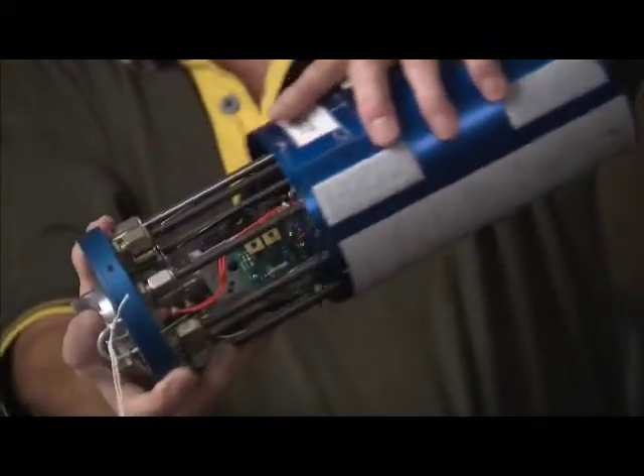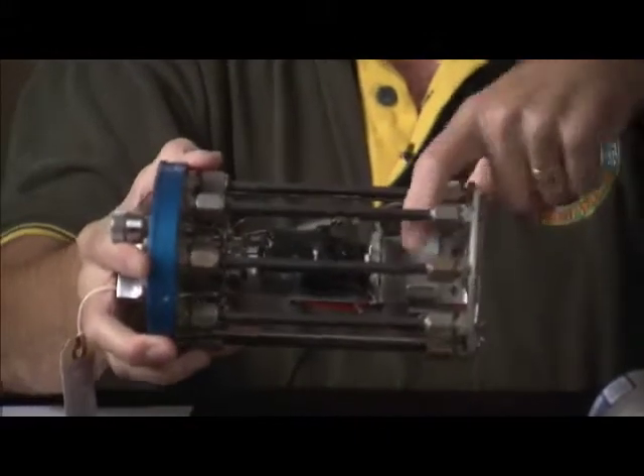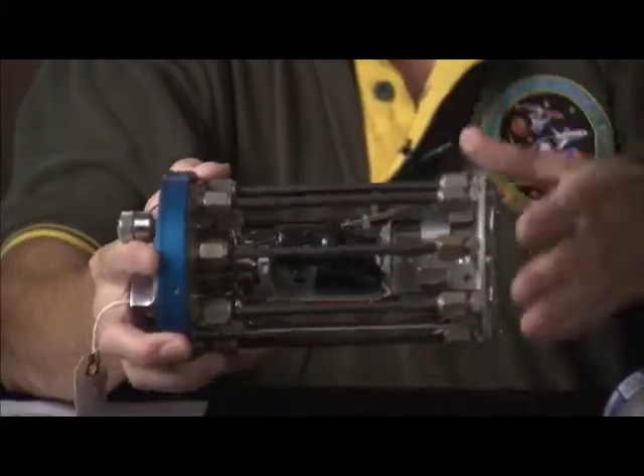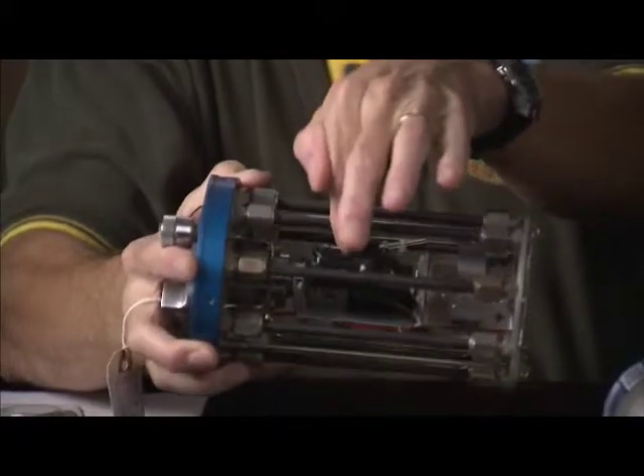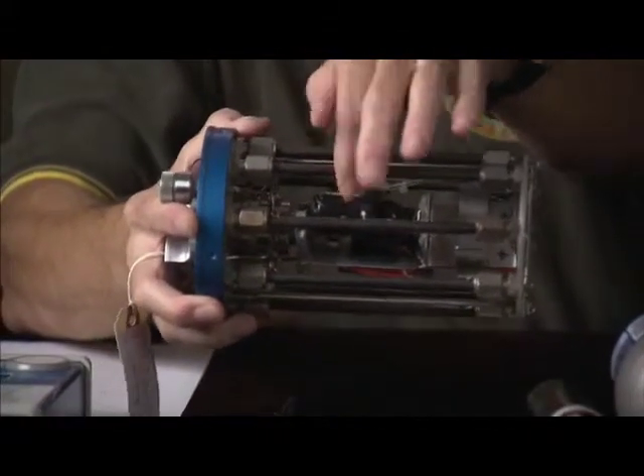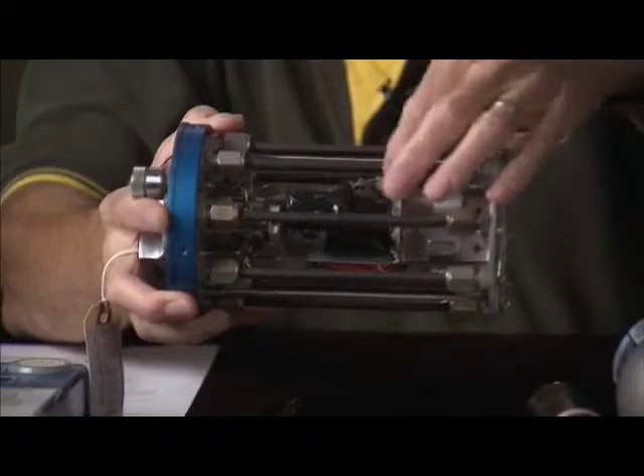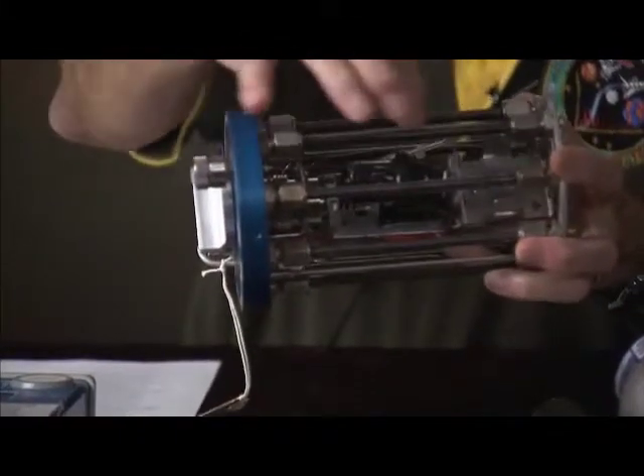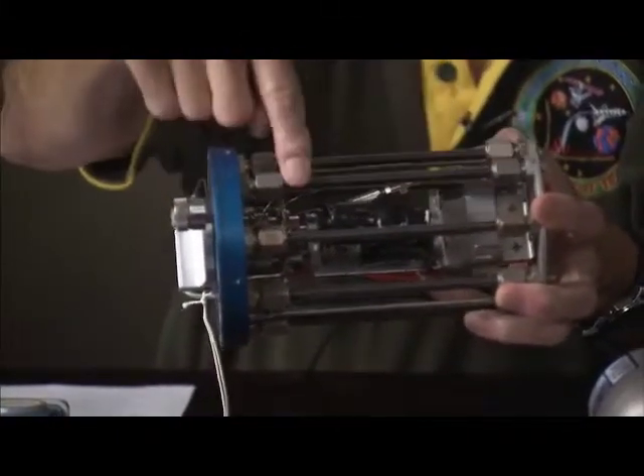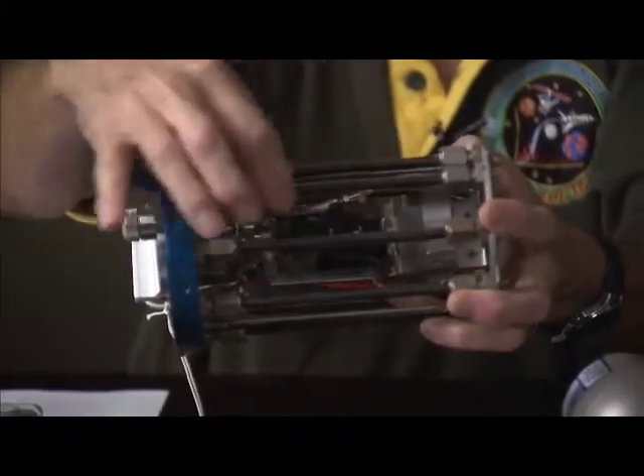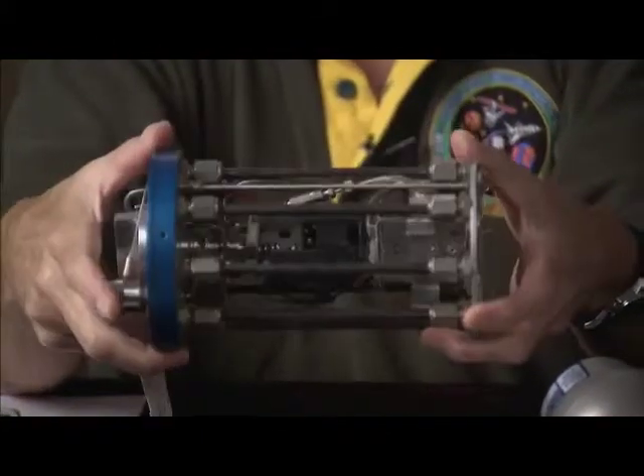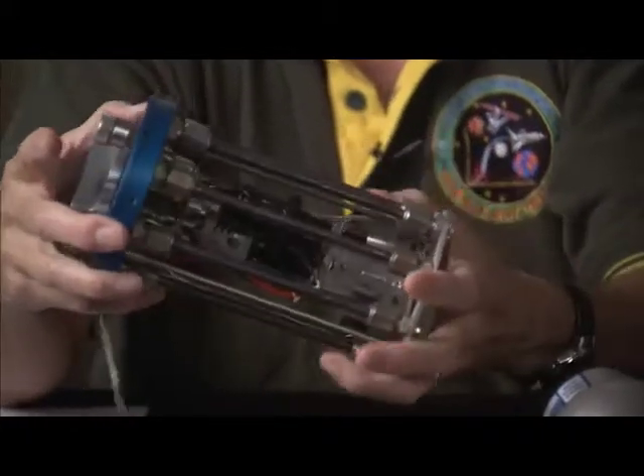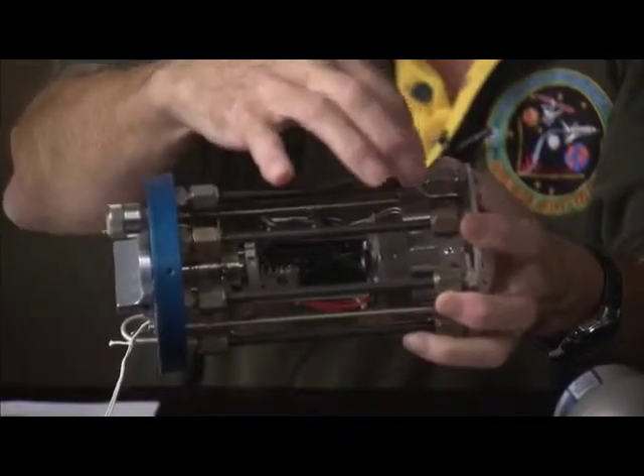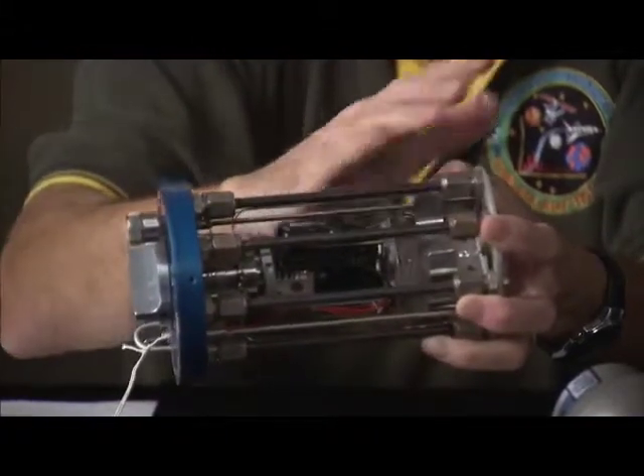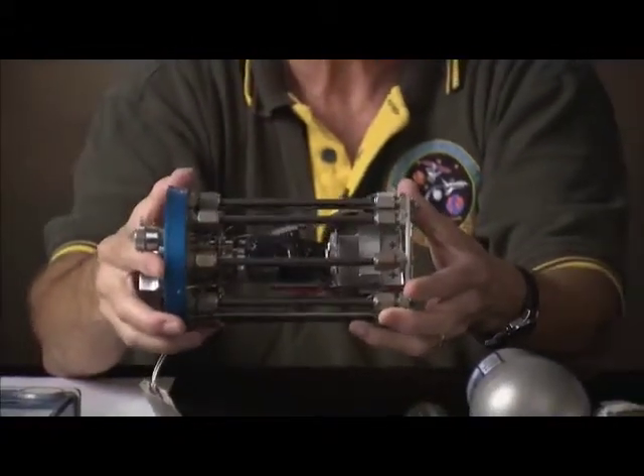The way this thing functioned was this: there was a holder for batteries, 2 B-size cells, a pump similar to one you might have in an aquarium, and tiny tubings that would run the gas around and deposit the contaminants in long tubes filled with absorbent material. This device was brought back into the lab, and hot air was run through these tubes to desorb the pollutants, which were then put into a GC mass spectrometer.